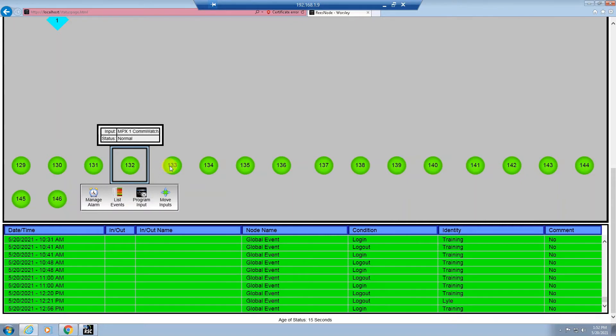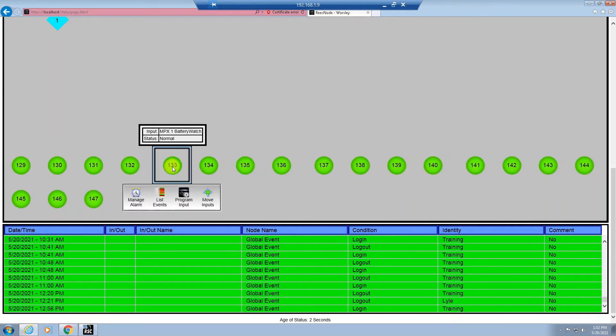Input 133 is to monitor batteries. If you have a wired or wireless system, the REIS monitoring system monitors the batteries and will give you a warning before the battery goes into a dead condition. This will give you the opportunity to swap the battery out and put the condition of that input back into a normal condition. While you have a battery watch condition, the transmitters will still be transmitting the data until the battery is replaced.